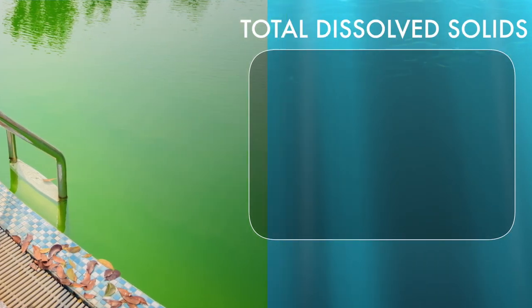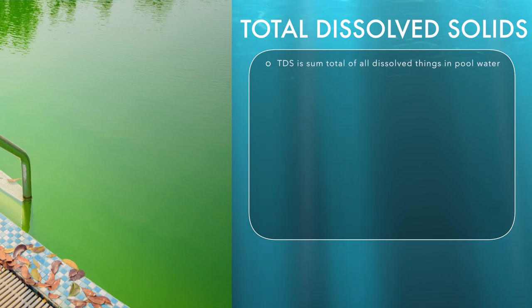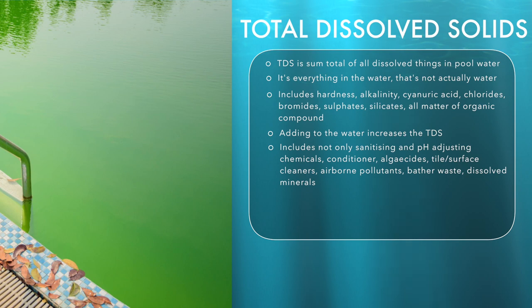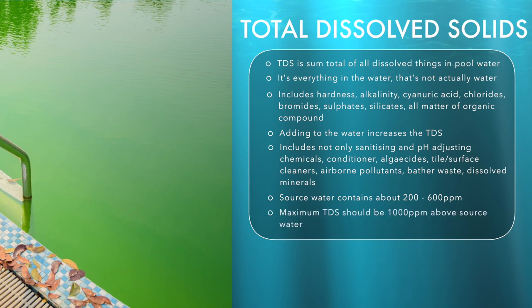Total Dissolved Solids, or TDS, is the sum total of all of the dissolved things in swimming pool water — it's everything in the water that's not actually water. It includes hardness, alkalinity, cyanuric acid, chlorides, bromides, sulphates, silicates and all manner of organic compounds. Every time you add anything to water you are increasing the TDS. This includes not only sanitising and pH adjusting chemicals, but also conditioner, algicides and tile surface cleaners. It includes airborne pollutants and bather waste, as well as dissolved minerals in the water. Source water contains about 200 to 600 parts per million, and the maximum TDS should be 1,000 parts per million above the source water level.